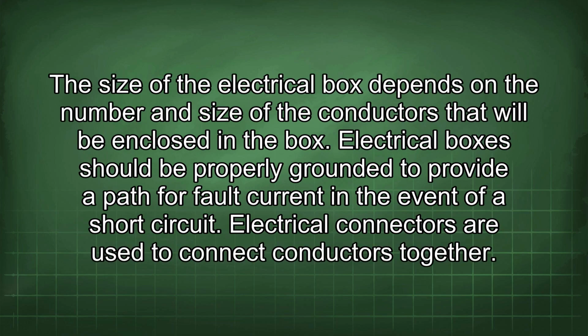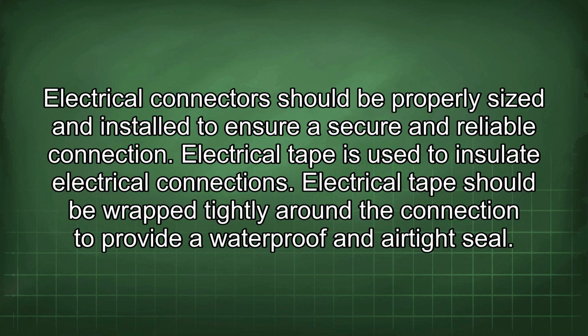The size of the electrical box depends on the number and size of the conductors that will be enclosed in the box. Electrical boxes should be properly grounded to provide a path for fault current in the event of a short circuit. Electrical connectors are used to connect conductors together. Electrical connectors should be properly sized and installed to ensure a secure and reliable connection. Electrical tape is used to insulate electrical connections. Electrical tape should be wrapped tightly around the connection to provide a waterproof and airtight seal.